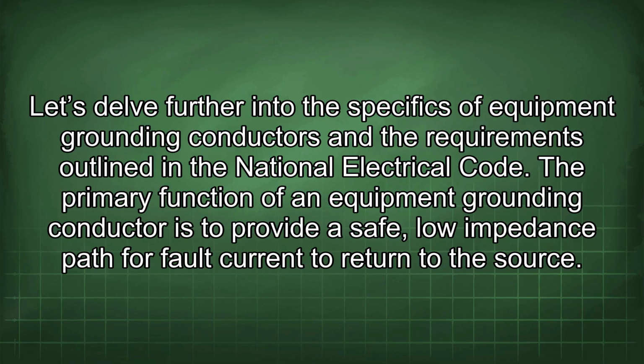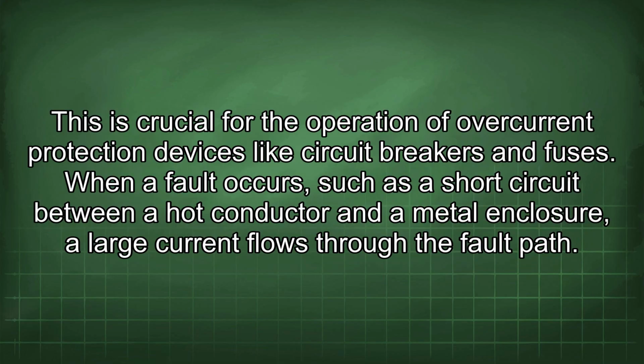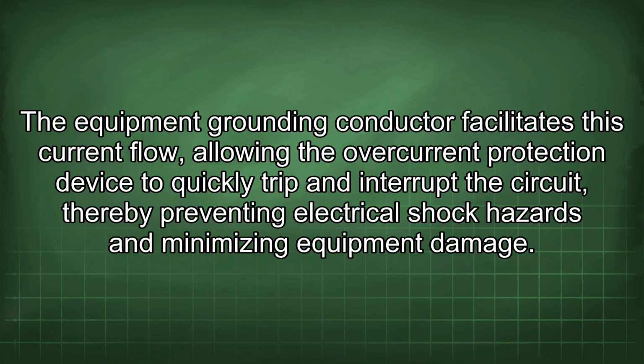National Electrical Code. The primary function of an equipment grounding conductor is to provide a safe, low impedance path for fault current to return to the source. This is crucial for the operation of overcurrent protection devices like circuit breakers and fuses. When a fault occurs, such as a short circuit between a hot conductor and a metal enclosure, a large current flows through the fault path. The equipment grounding conductor facilitates this current flow, allowing the overcurrent protection device to quickly trip and interrupt the circuit, thereby preventing electrical shock hazards and minimizing equipment damage.